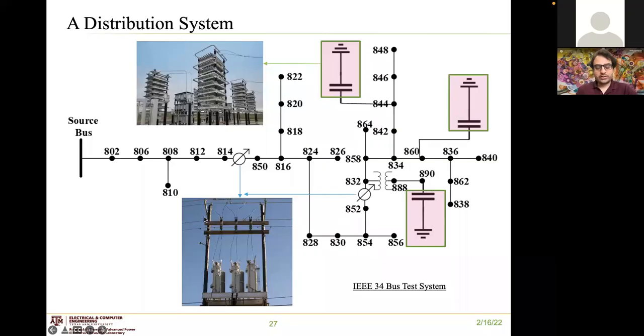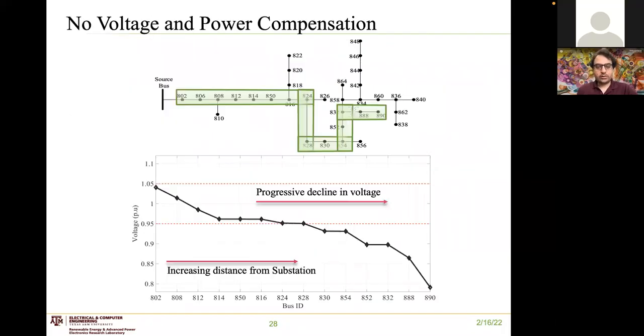Voltage regulators are placed to control the voltage along the length of the feeder, and we have capacitor banks to minimize losses since they correct the power factor. Here is the same distribution feeder, but in this case we have removed the voltage regulators and capacitor banks.